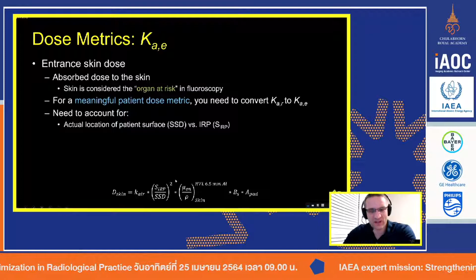So let's look at this equation and see what all the values are. When you want to consider the dose to the skin, we have the air kerma, the cumulative air kerma at the international reference point. The next thing we need to know is where the patient is with respect to that reference point. We know where that reference point is. Remember, I gave you that table. You can either measure it from the floor to the reference point, or from the focal spot of the X-ray tube to the entrance point. We also need to know the distance of the patient, so maybe the floor to the table.